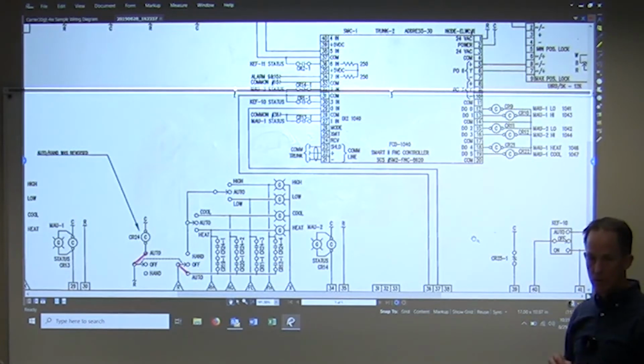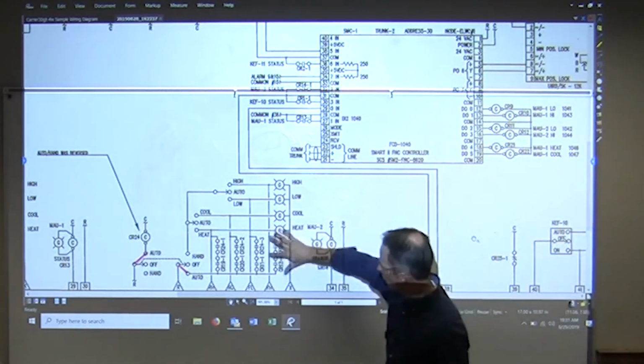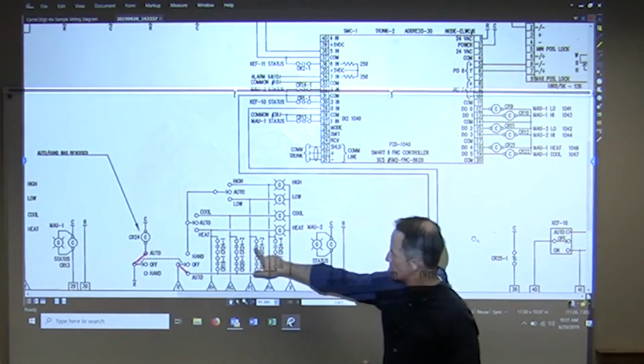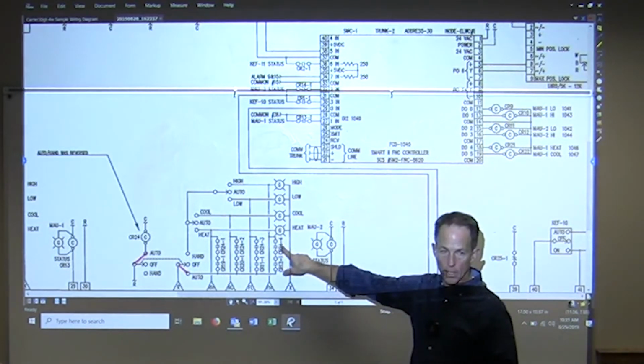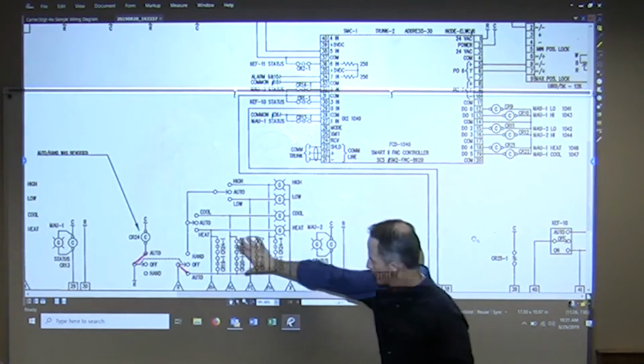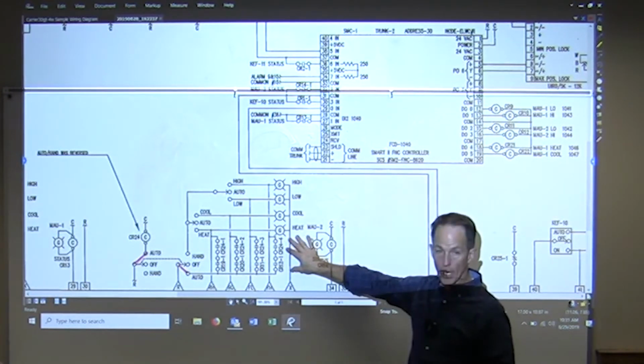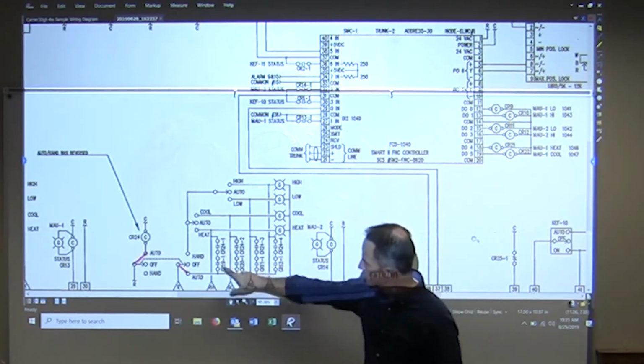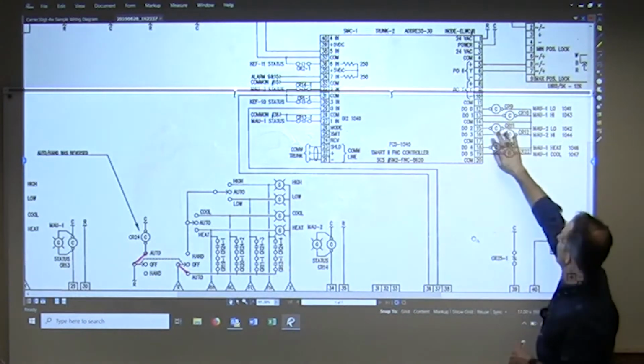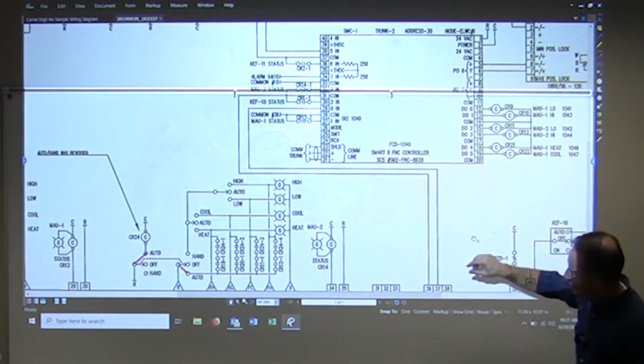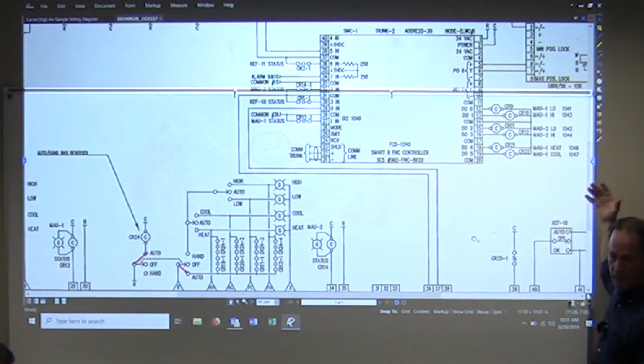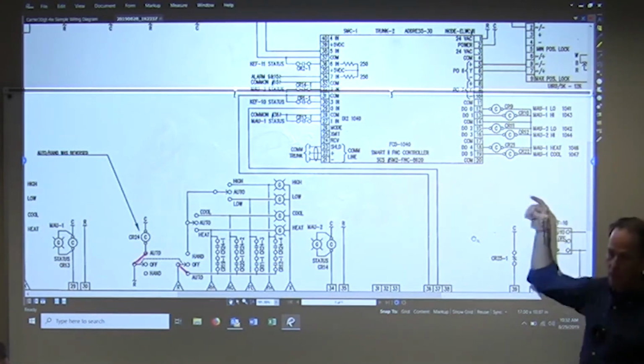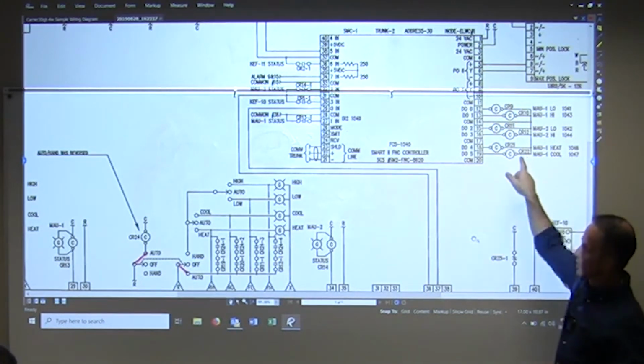It's energized. Okay, and how many contacts does it energize or are part of CR24? Okay, so we're going all the way through here, right? 24, 1, 2, 3, and 4. All right, so this piece of the circuit has to do with our auto. And if we follow these relays, they're all up right in here, except 19 and 20 are on another page. Okay, if we were to go to the first one, we would see 21, 22 on that.